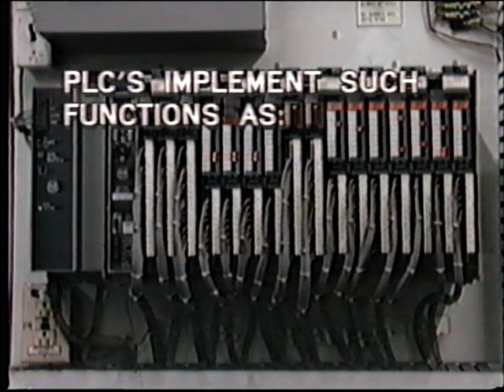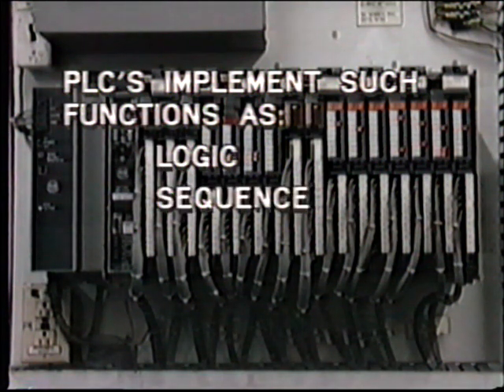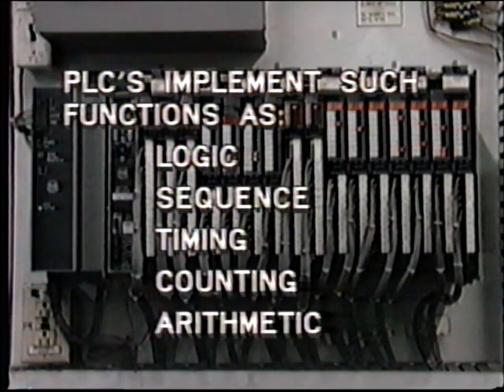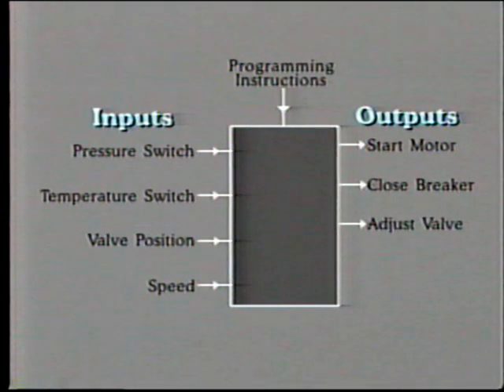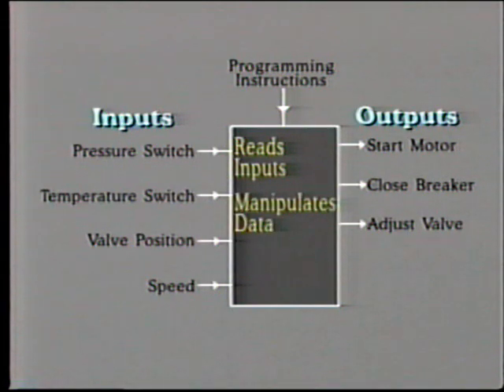A definition of a PLC could be given as follows. It is a digital electronic device that contains instructions in its programmable memory, which enables it to implement specific functions such as logic, sequence, timing, counting, arithmetic. This simple block diagram shows the principle. Inputs from pressure switches, temperature switches, and other sources are fed into one side of the controller, a black box in this instance, and outputs to solenoids, motors, relays, etc., exit from the other side. The controller has to continuously read the status of the inputs, manipulate the data according to its pre-programmed instructions, and then set the outputs accordingly.